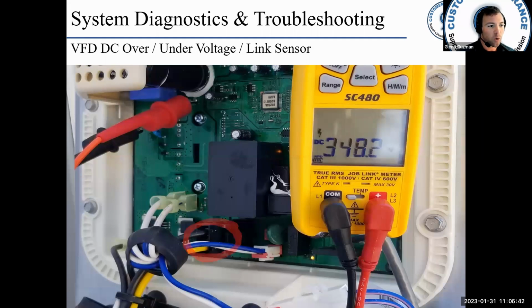Okay, now if you want to know what the DC voltage is, you can see it on the UI, and that's great. But if you want to read it directly with your meter, so you know that what you're seeing is what the unit is seeing as well, there are two terminals on here. It's kind of hard to see from the picture because the alligator clips are on there, but there are two DC terminals here that you can grab with your alligator clips, turn the unit on, and then read your DC voltage, okay? So check your voltage at the UI, and then check it at the VFD itself.